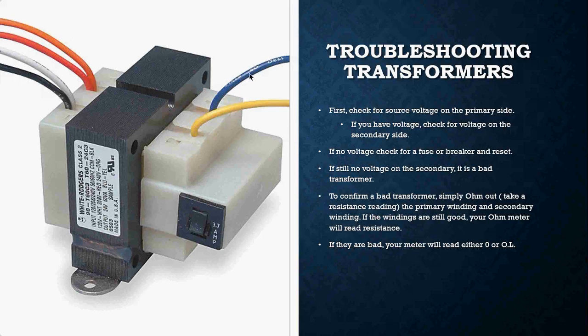On the secondary side, all you have is a blue and a yellow wire — that's your output. When troubleshooting, first make sure you have voltage on the primary side, because we're using the primary side to induce voltage onto the secondary. If nothing is happening on the primary, nothing is going to happen on the secondary. Check for voltage on the primary, then check for voltage on the secondary. If there is no voltage on the secondary side, chances are the transformer is no good — but do a couple more steps before you condemn it.